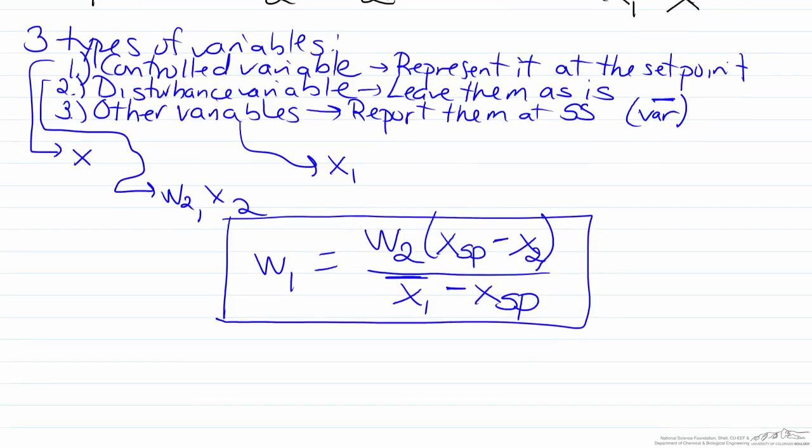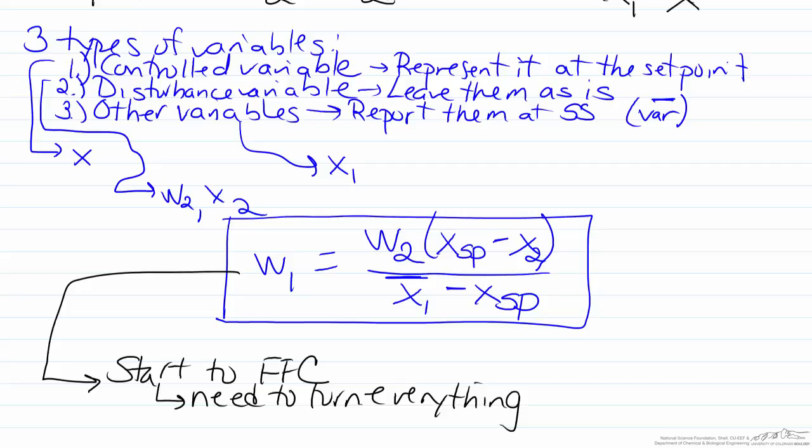An important point is this represents a start to the feedforward controller. What is left is we need to turn everything into signals, because remember that transmitters and control schemes don't report back fifty gallons per minute, they report back particular signals: twenty percent transmitter output, forty percent transmitter output, etc.